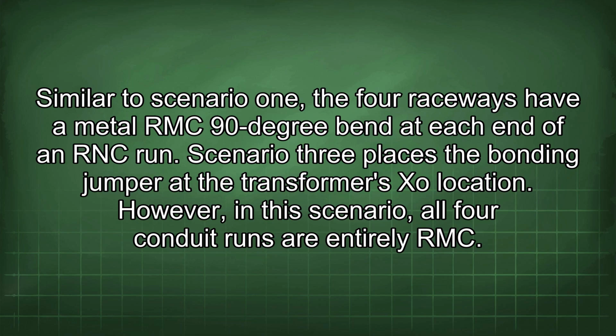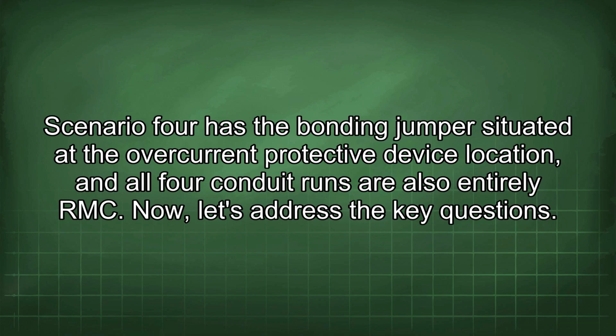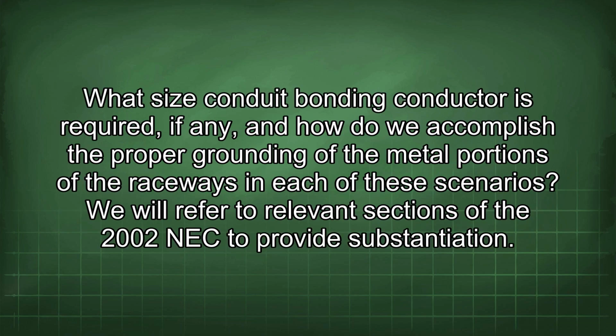Scenario 3 places the bonding jumper at the transformer's XO location. However, in this scenario, all 4 conduit runs are entirely RMC. Scenario 4 has the bonding jumper situated at the overcurrent protective device location, and all 4 conduit runs are also entirely RMC. Now let's address the key questions. What size conduit bonding conductor is required, if any, and how do we accomplish the proper grounding of the metal portions of the raceways in each of these scenarios?